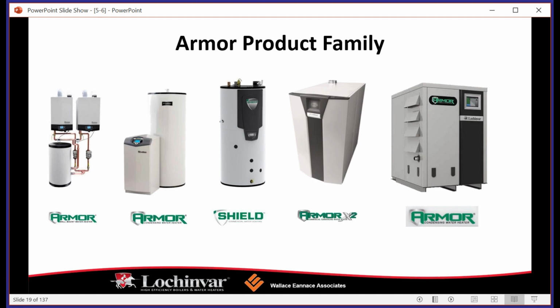The Armor product family is our water heating product family. And if you just briefly look over this slide, you're going to see that the Armors look very similar to the Crests and the FTXLs and the Knights, because essentially the cabinets and the layout are all very similar. Again, the condensing technology, the modulation, the turndown, all that tech leads across the product lines, and we're using it all similarly. So again, the cabinets are very similar. The biggest differentiator is going to be what kind of materials are being used for a water heater, because you do have the potable water. You want to make sure that you're only using bronze, stainless steel, and brass in order to make sure that you're not using anything that people can't drink from.